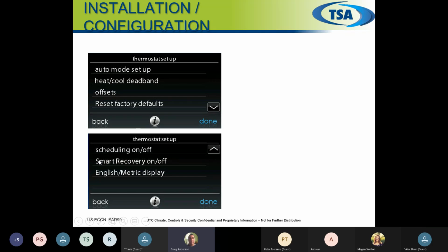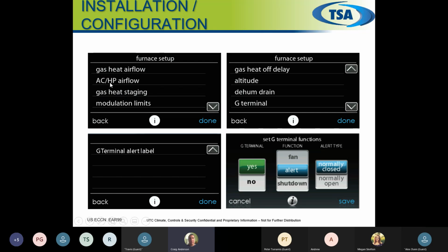Like any standard stat, scheduling on and off, smart recovery, stuff like that. This is where we can get into tweaking a little bit. Gas heat airflow, we can go in and tweak it up and down a little bit. But it's already checked the static pressure, so you're just tweaking it. Heat pump, AC airflow as well. Gas heat staging, you can tweak it a little bit, speed up the first stage and slow down the second stage, stuff like that. If you have a modulating furnace, you'd have modulating limits you can play with when it's going to go from 40 to 100, or you want to start it off at 60 and go to 100, stuff like that. A lot of little things you can play with.